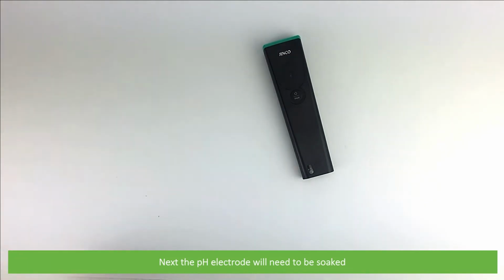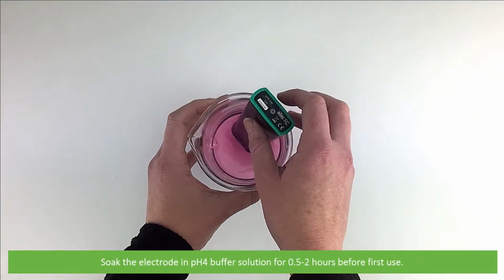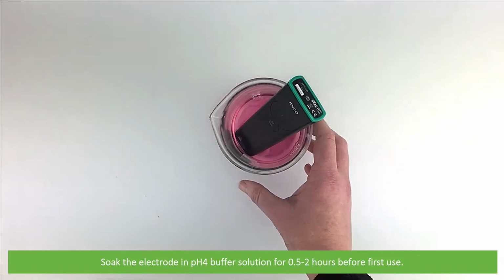Next, the pH electrode will need to be soaked. Soak the electrode in pH 4 buffer solution between half an hour and 2 hours before the first use.